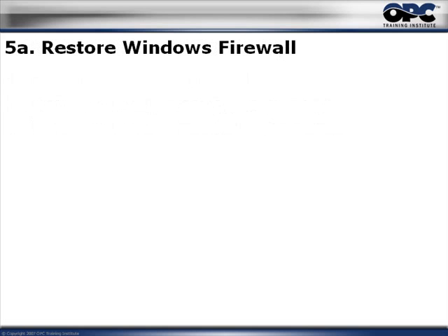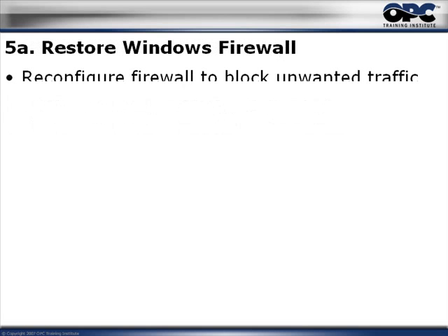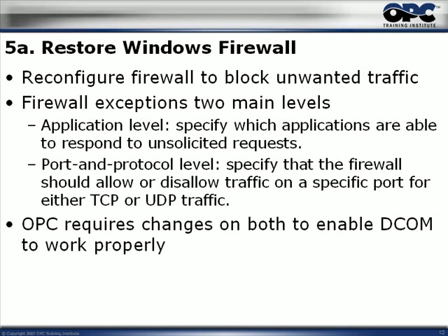Let's go to the first part, which is to restore the Windows firewall. It's fairly easy — all we need to do is put the firewall back up and it's going to block unwanted traffic. But remember that this time, we need to provide exceptions on two levels: first, the application level, and second, the port and protocol level. Don't forget that for DCOM you need port number 135. OPC requires changes on both application level and port and protocol level to make sure DCOM is working properly.